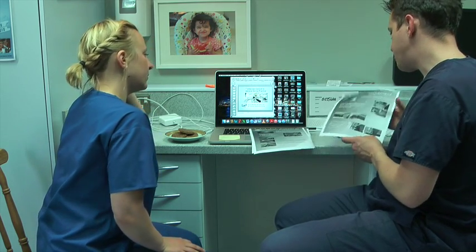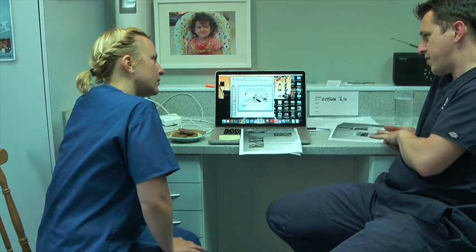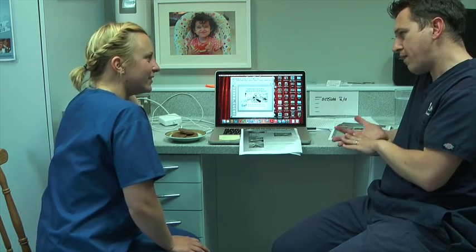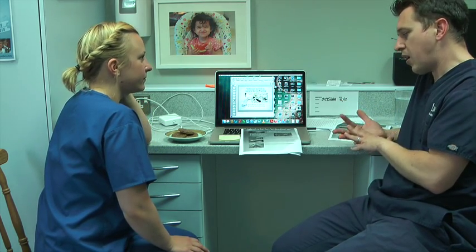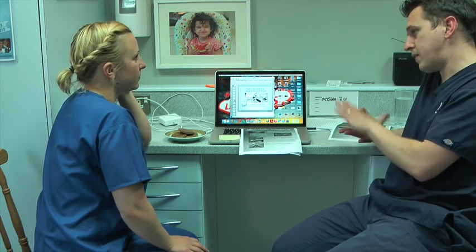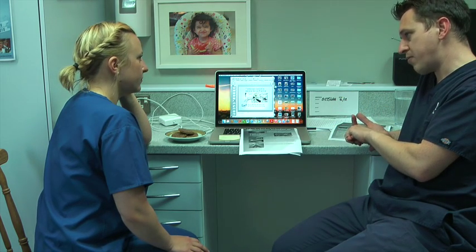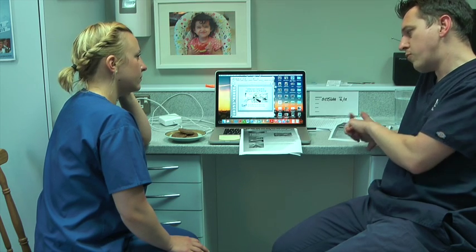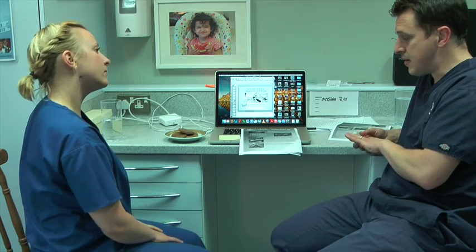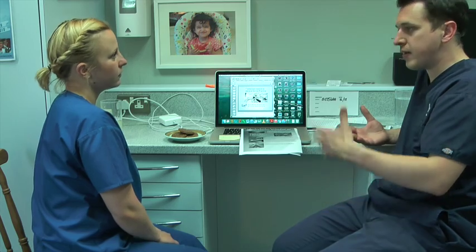Where we fall short is where? Manual cleaning, because it's hard to validate manual cleaning. Excellent, good stuff. So we can't validate the manual cleaning. We can't say for sure that we are persistently doing manual cleaning effectively and efficiently every time. The only way that we're going to be able to validate it properly is with a washer disinfector. So we fall short on that. At the minute we're looking to do the ultrasonic cleaning as well, ultrasonic bath cleaning. Whether we incorporate that as part of the manual cleaning after we've manually cleaned, that's probably something we'll look at doing.